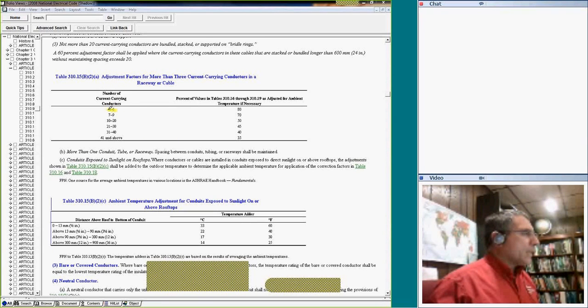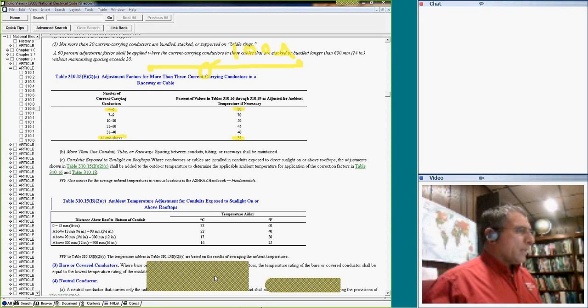So if I have more than 3 current-carrying conductors, guys, I can derate. So if I have up to 6 conductors, I can cut them by 80%. If I have more than 41 conductors in a raceway, you can cut by 35%. What does that mean? So a very quick example. Suppose I have a conductor, and this conductor was supposed to carry 100 amps, right? If I put this conductor under these circumstances, let's say 40 of these conductors in one conduit, you will take the 100 and multiply it by 0.4. That's what your beautiful 100 amp conductor is now carrying: nothing but 40 amps.